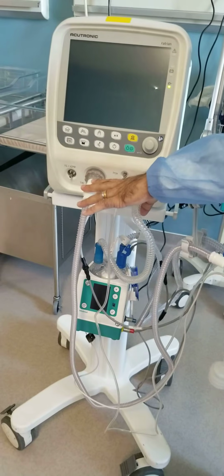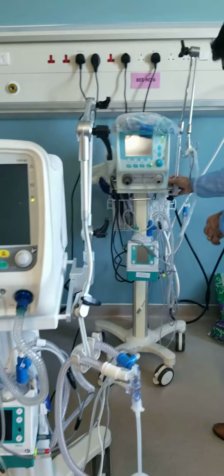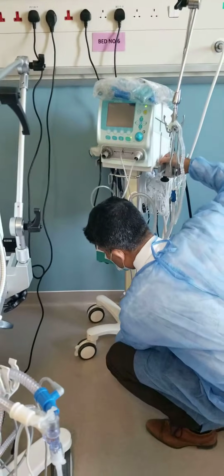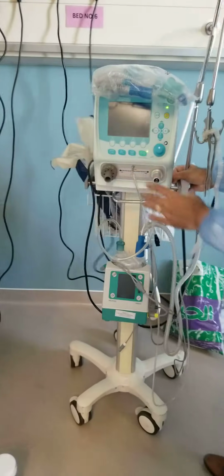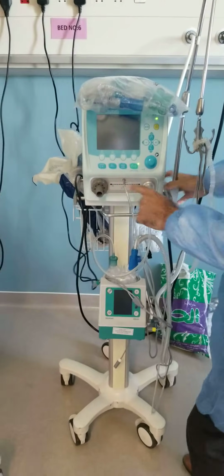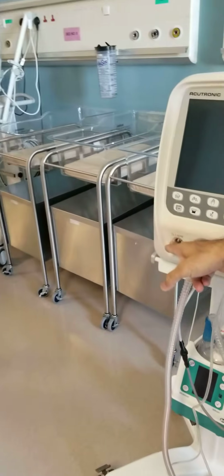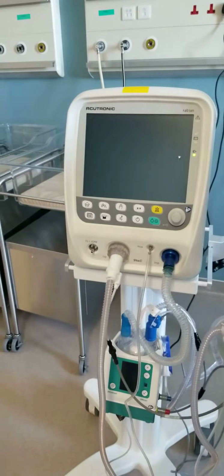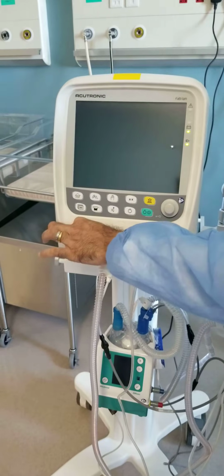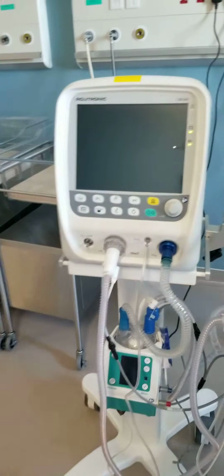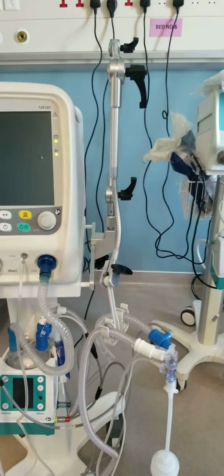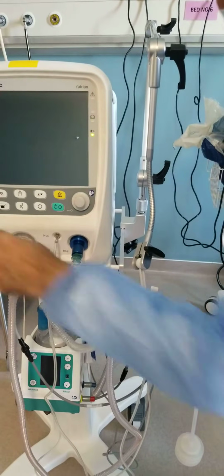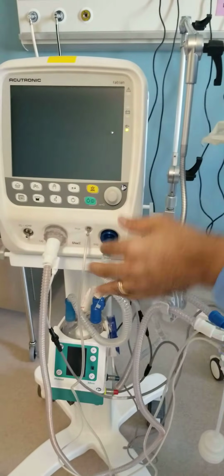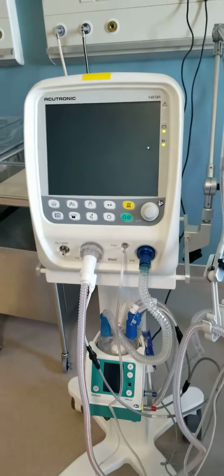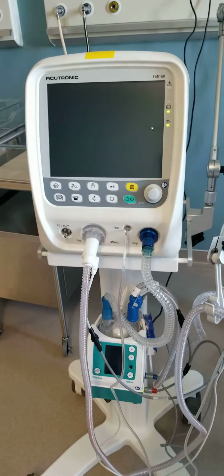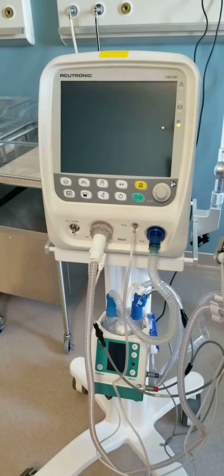Whenever you're using non-invasive, just like I showed, and I was mentioning about these 2, that's when we have this option. So when you're using non-invasive, the only thing is, instead of this tube, I will connect it from here. That is the only thing. You can still use the same. But it's not a flow interrupter. It's a continuous flow CPAP. It's a true membrane oscillator. It's not a flow interrupter.